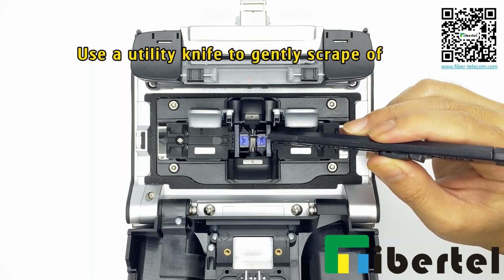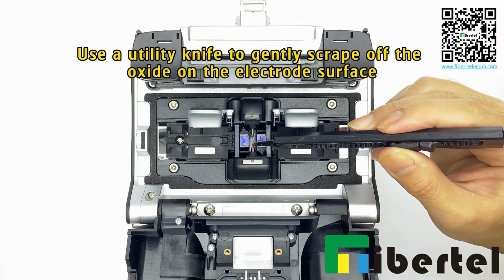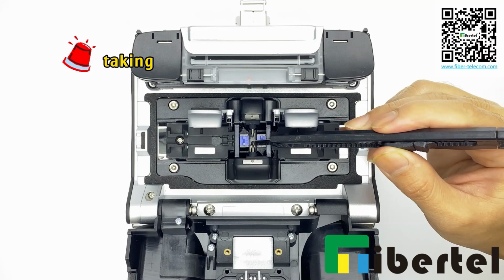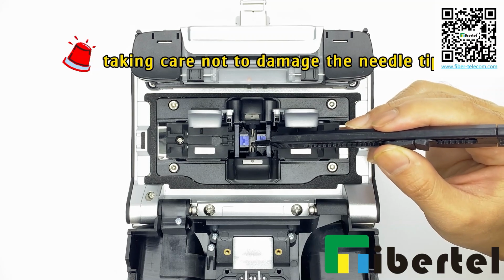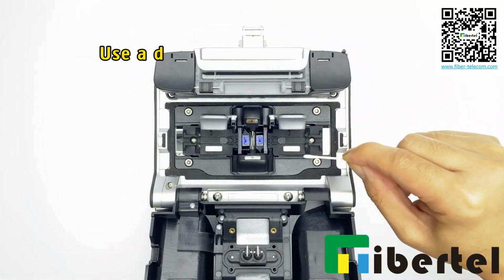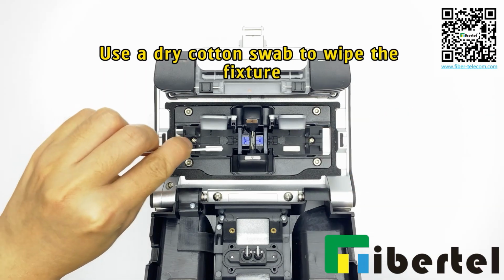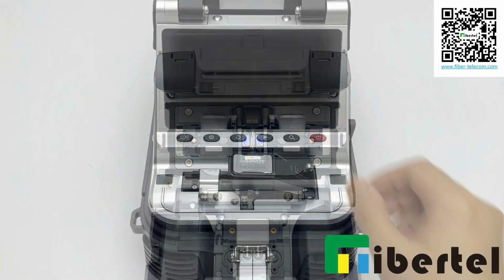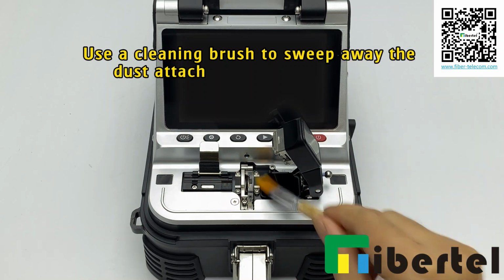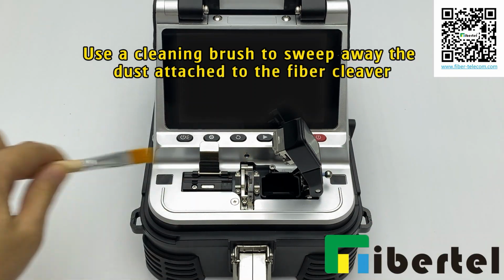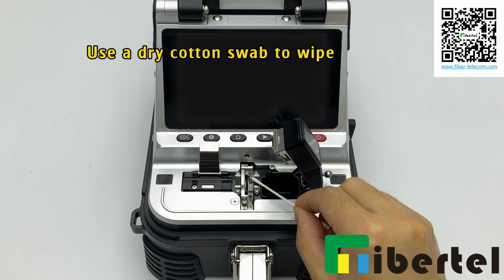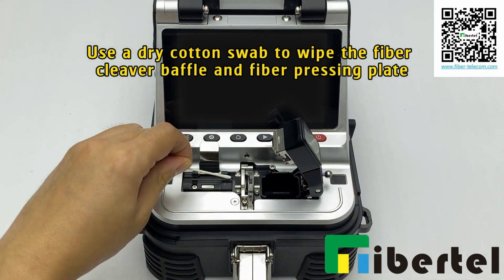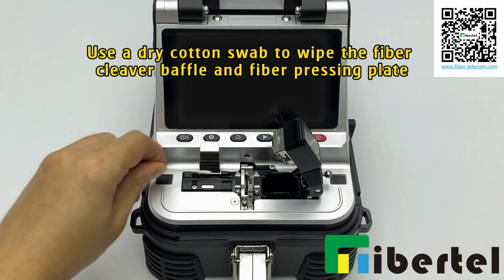Use a utility knife to gently scrape off the oxide on the electrode surface, taking care not to damage the needle tip. Use a dry cotton swab to wipe the fixture. Use a cleaning brush to sweep away the dust attached to the fiber cleaver. Use a dry cotton swab to wipe the fiber cleaver baffle and fiber pressing plate.